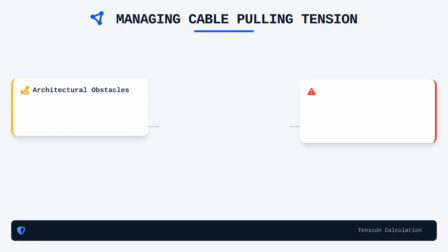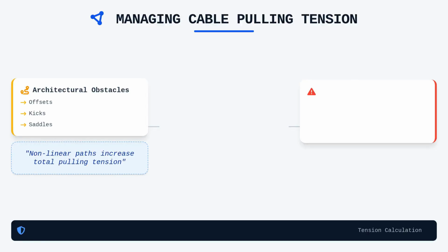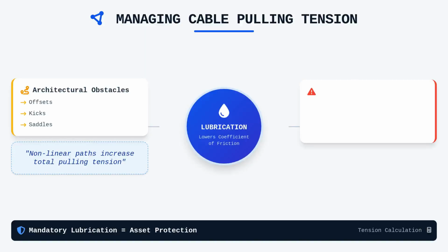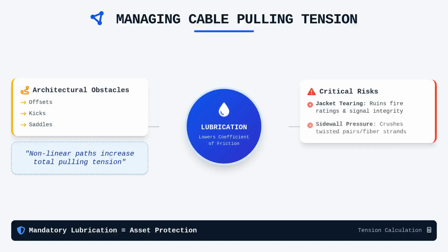When architectural obstacles force a nonlinear path, we introduce offsets, kicks, and saddles to bypass structural elements. Each of these physical deviations adds to the total pulling tension, which is essentially the force required to slide the cable through the raceway. You must calculate this tension by considering the coefficient of friction between the cable jacket and the conduit wall. This is exactly where specialized cable pulling lubricants become mandatory. These substances lower the coefficient of friction, acting as a microscopic buffer. Without adequate lubrication, you risk catastrophic jacket tearing, which renders the cable useless in terms of fire ratings and signal integrity. Furthermore, we must monitor sidewall pressure to prevent the crushing of the internal twisted pairs or the fracture of fiber strands during the installation process itself.